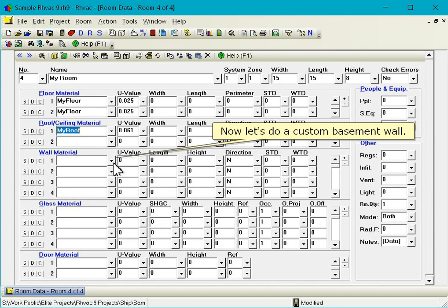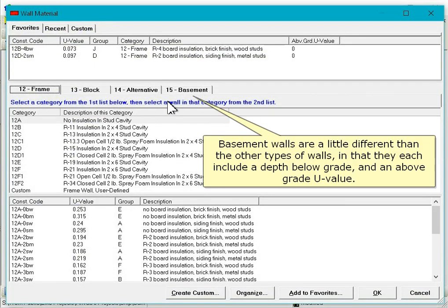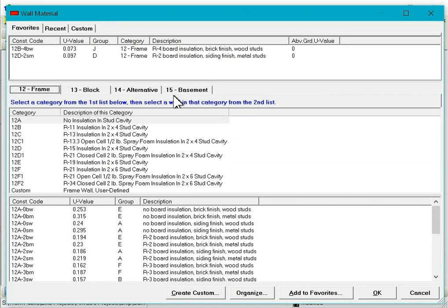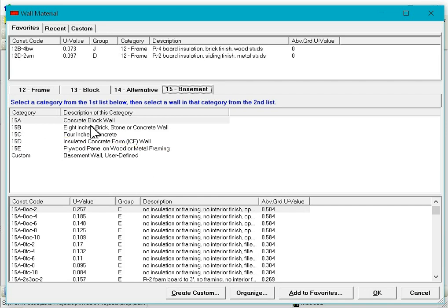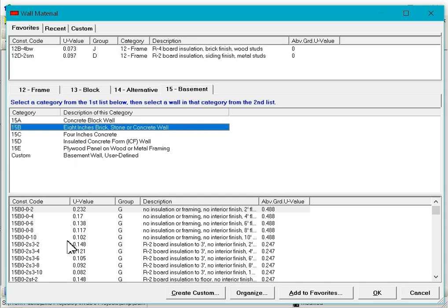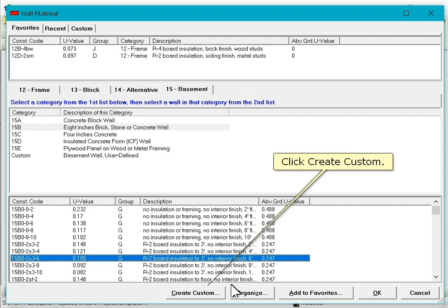Now let's do a custom basement wall. Basement walls are a little different than the other types of walls in that they each include a depth below grade and an above grade U-value. Now select the category that closely matches our new wall, and finally single click on a wall that closely matches our new wall. Click Create Custom.